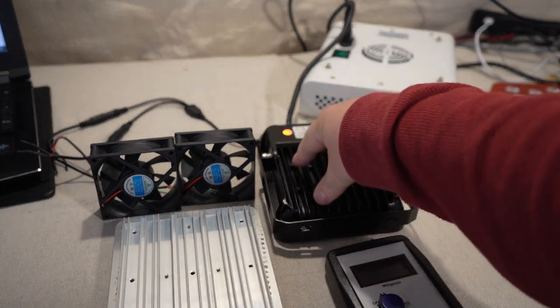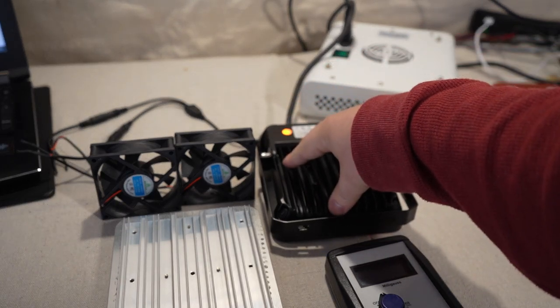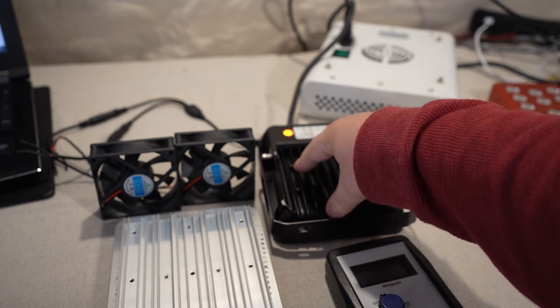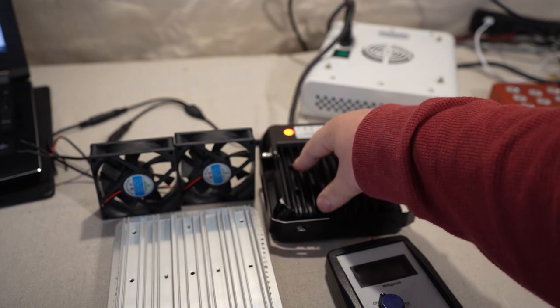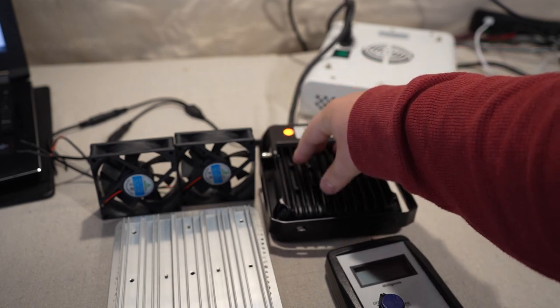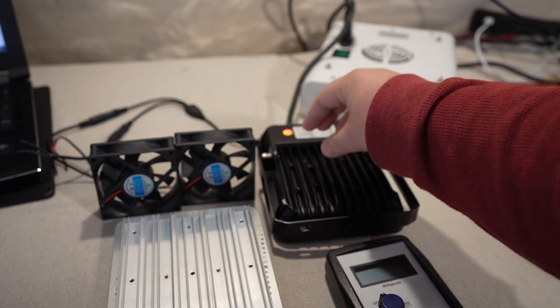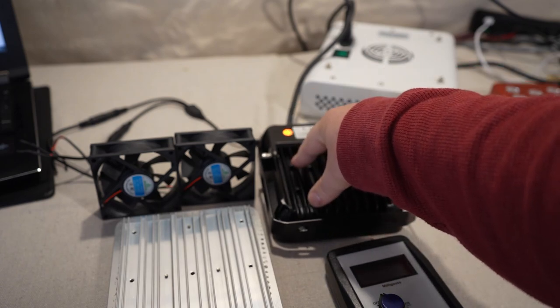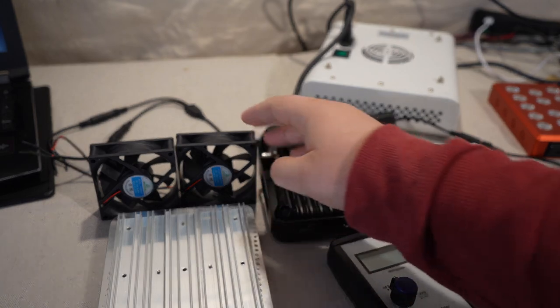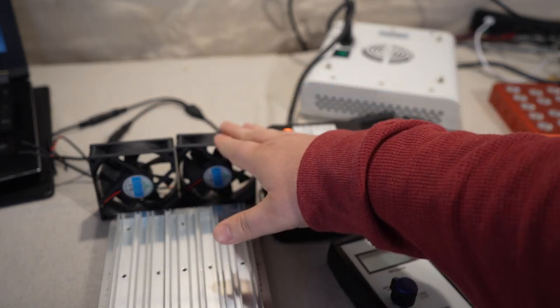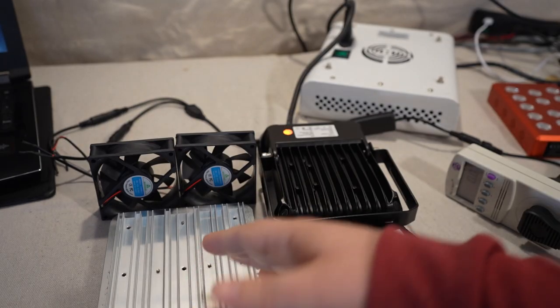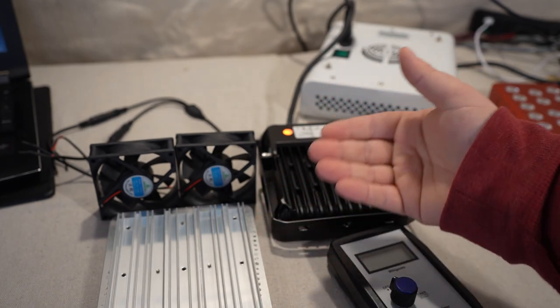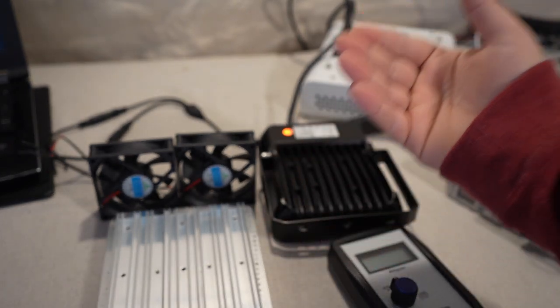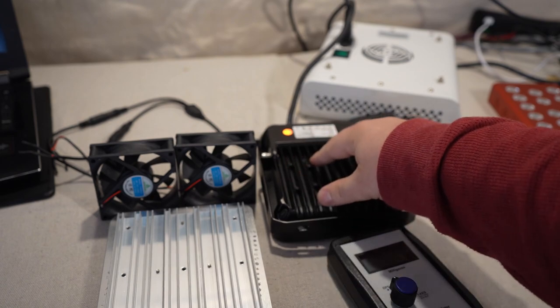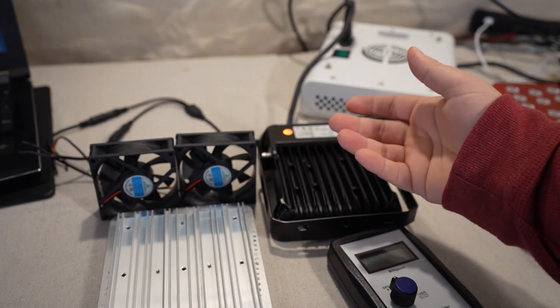Or you can take more time. It'll cost more money. It'll be heavier, which again, we might not want weight when we have heavy devices. But it should last longer. It should still do a good job if you balance the heat load. So that's about it. If you've got fans, they are a cheap way of cooling, and they're very effective at cooling. But they could fail in the long run. They could die out. They're lighter weight than using more metal, and they'll save you some money.